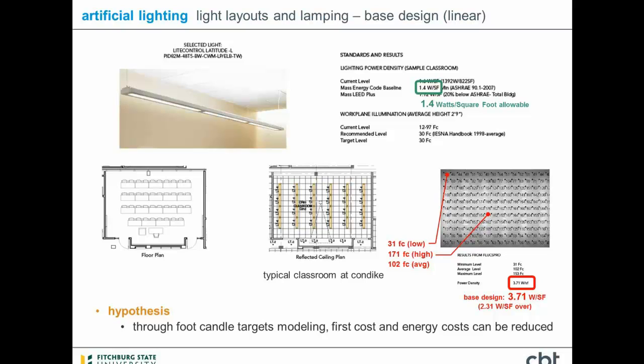Interestingly, what you can see right off the bat here is that the Mass energy code baseline is 1.4 watts per square foot, and our initial lighting layout was 3.71, which is well over the allowed limit for that particular space. On aggregate, we were actually right on for the entire building. Our electrical engineer had to run a check for the code, and we were right at the code baseline, but we certainly wanted to do much better than that.